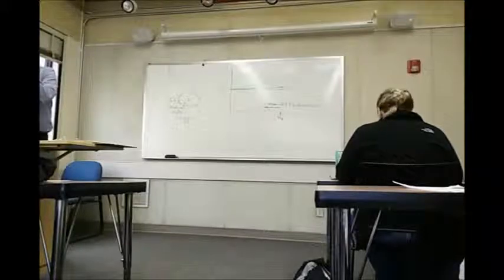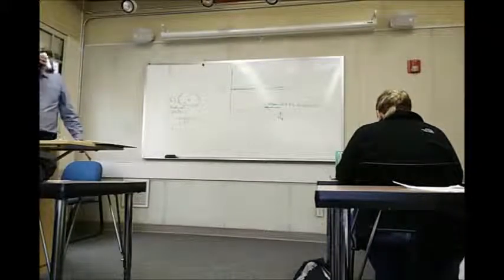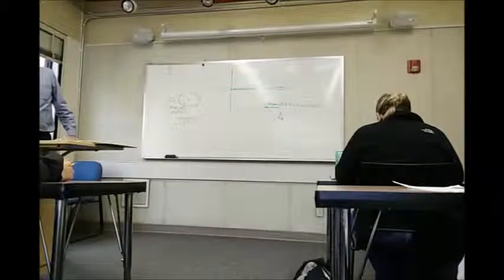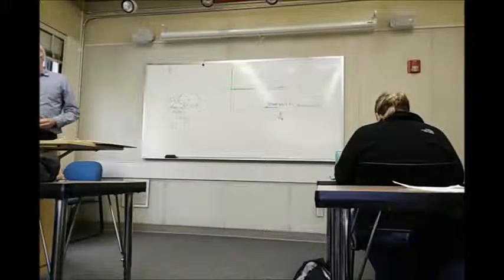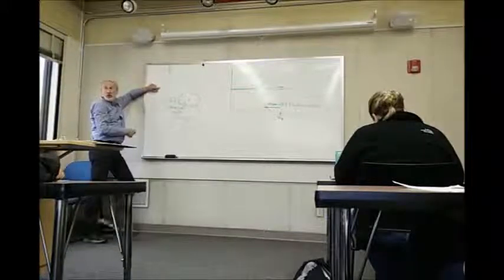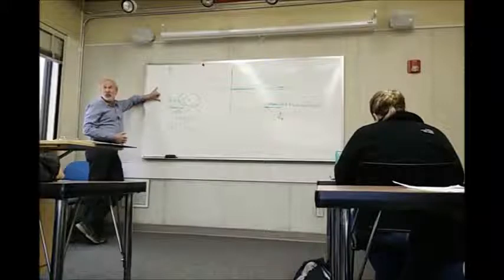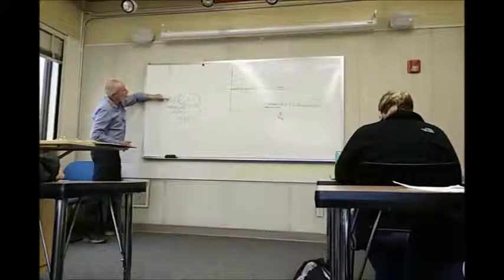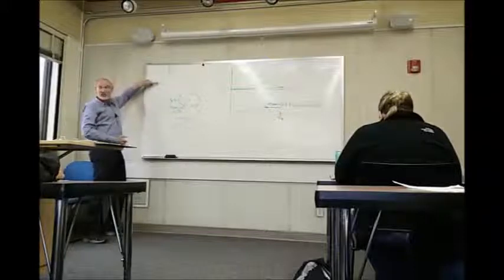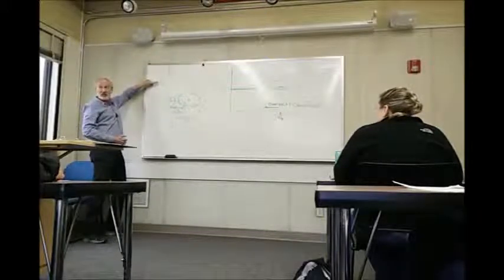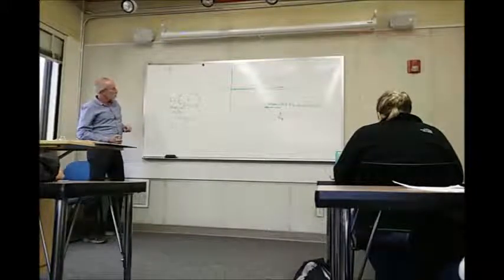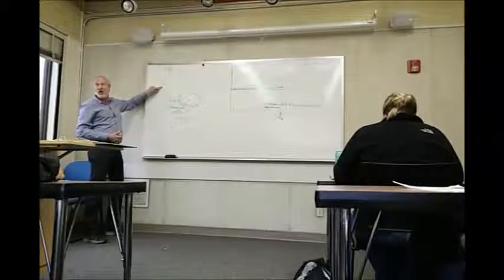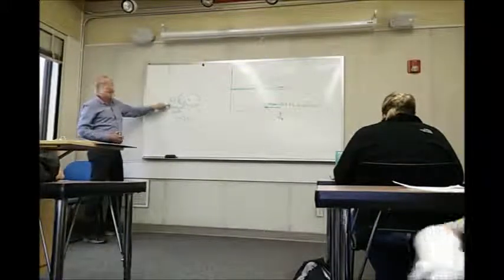Okay, Jed, what was your question? So then the V0 and H0, that's just it depends on the magnet you're using. It depends on the design of the machine. So that number could vary from machine to machine, but we're taking the ratio of these two, and that ratio stays the same no matter how big this is. This will always be exactly the same fraction of this, no matter what the size of the field. Okay, but we measure that ratio in parts per million? Yeah, so this in general is a million times greater than that.